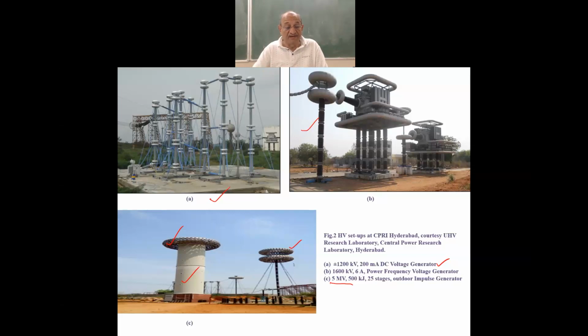For AC power frequency, you need a capacitive divider. And for DC measurement, you need a resistive divider. So the resistive divider appears to be somewhere in the last stage, if I'm not mistaken. This is where the resistive voltage divider is installed. So each high voltage generating equipment would also have a high voltage measurement system. As we have learned, sphere gaps are no more used for the measurement of high voltage. Dividers are used, and in all these three also we have suitable dividers, which we have also discussed.